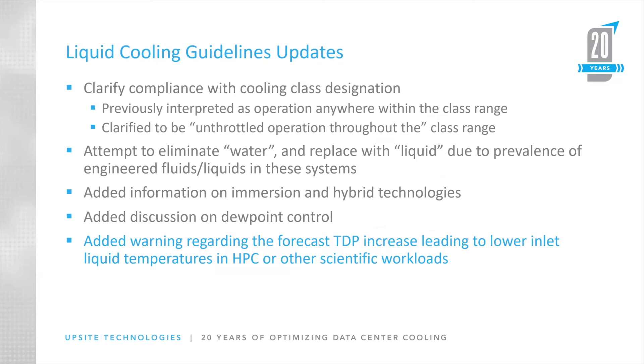We've also added a lot of information on immersion and hybrid liquid cooling technologies. We're seeing more scenarios where immersion isn't necessarily a bath in a tank laying on its side — we're starting to see vertical immersion, where you have liquid-tight chassis in a vertically stacked rack and flood the chassis in a vertical configuration. We also added a lot of discussion on dewpoint control, understanding condensation risks particularly during cold startup, and how insulation and ambient dewpoint control within your data center may impact that.